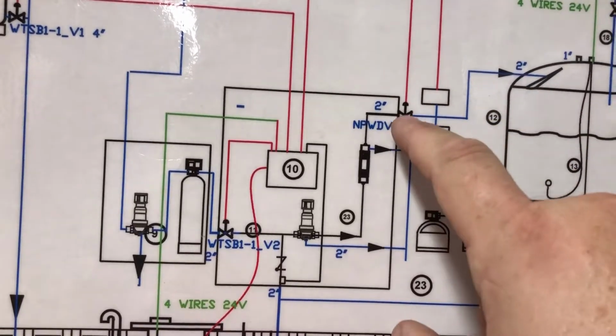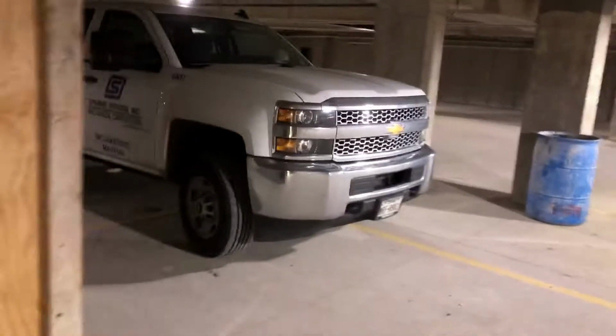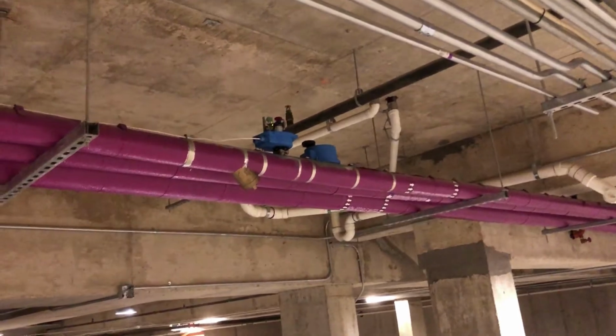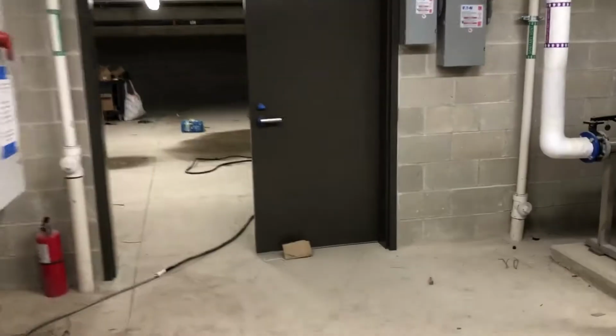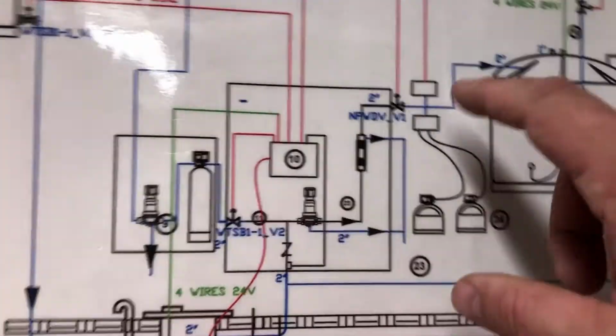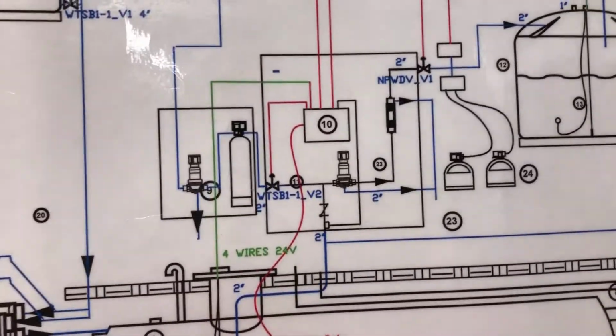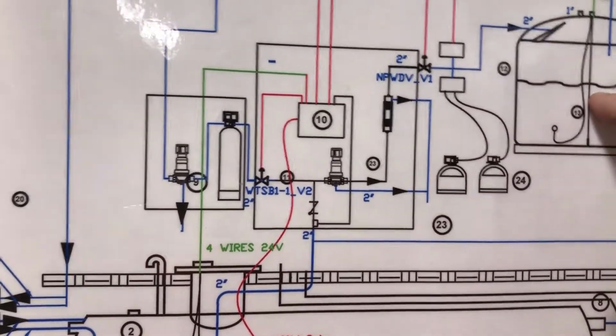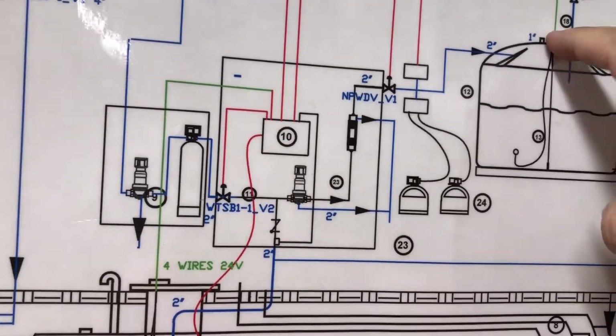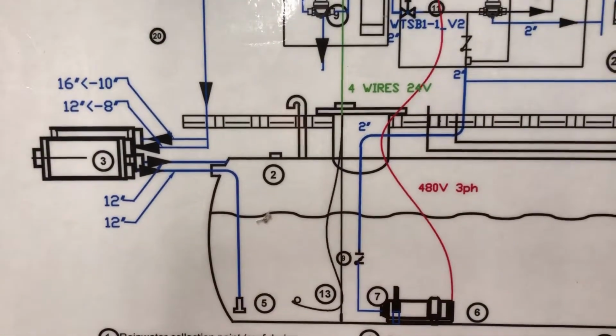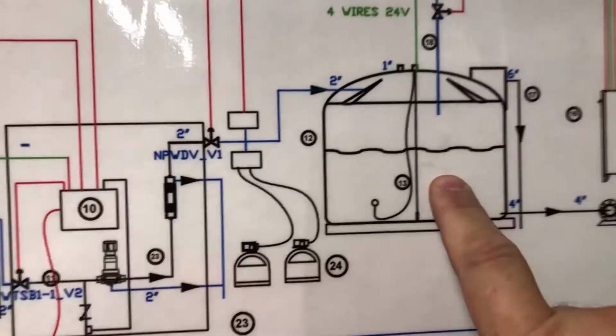And this valve is currently out this door and right up there. So, valve opens, pressure drops, pumps come on, water flows through the treatment, fills the day tank. When it fills the day tank, this sensor detects that. This controller, which is this one here, closes the valve, pressure rises, pump shuts off. So now we have water in our NPW day tank, which is situated.